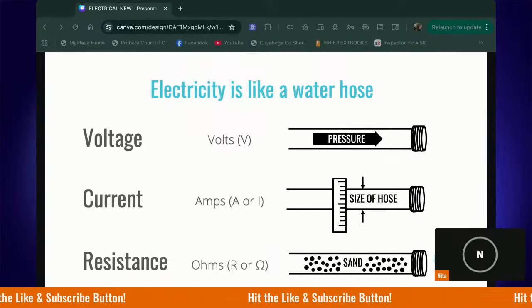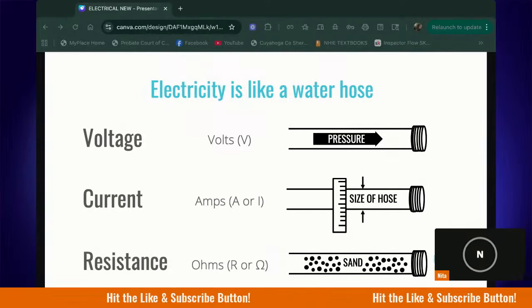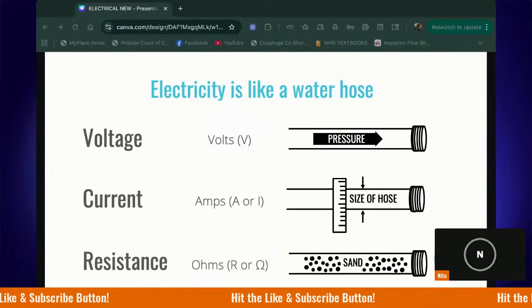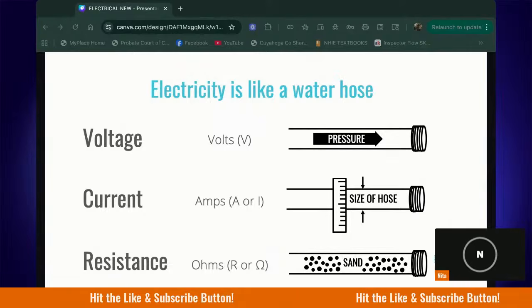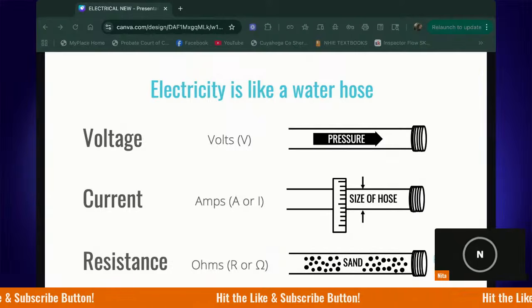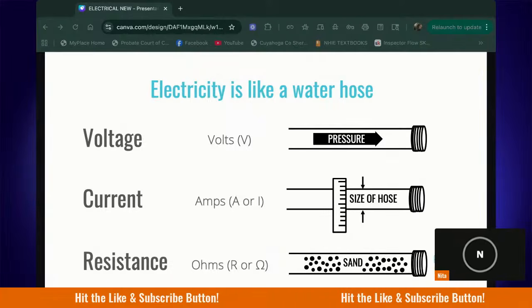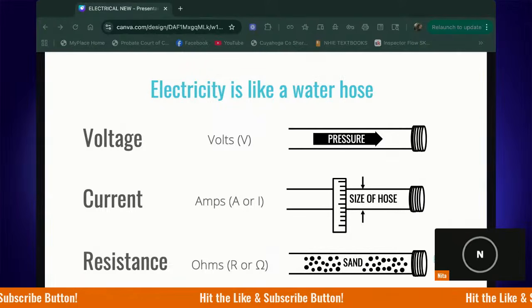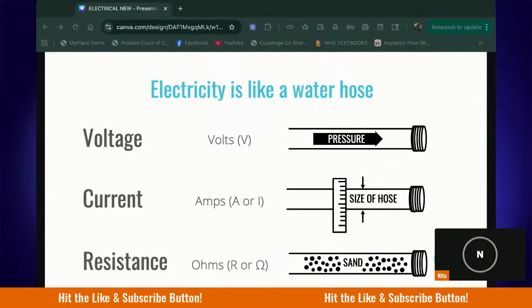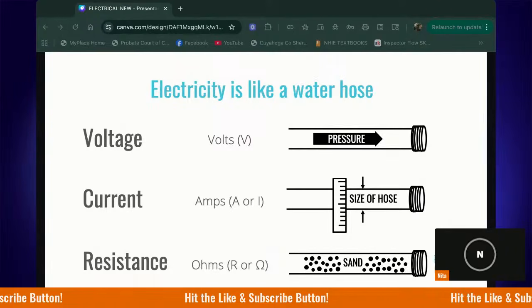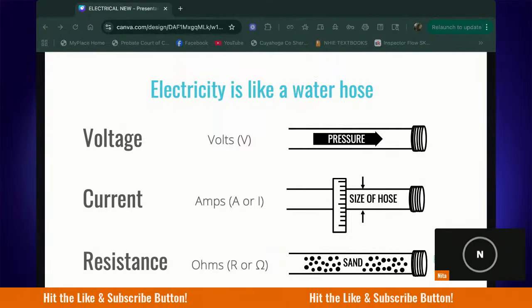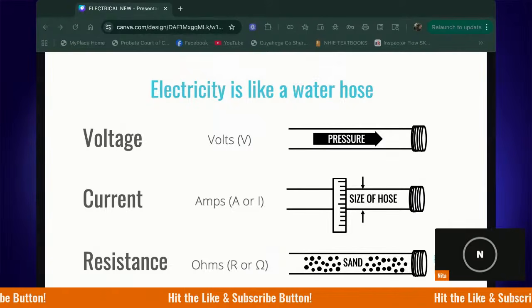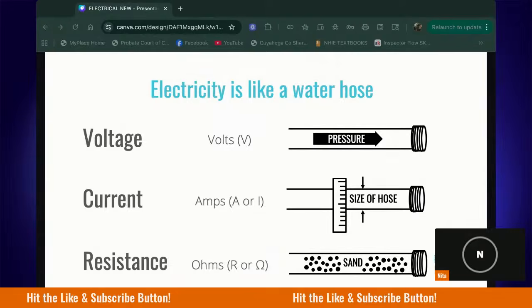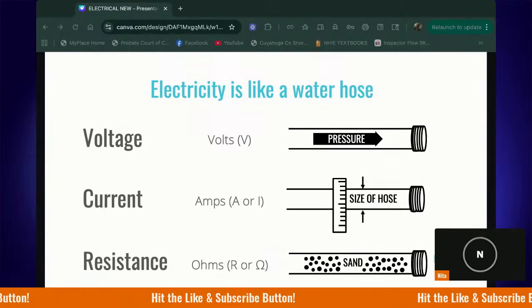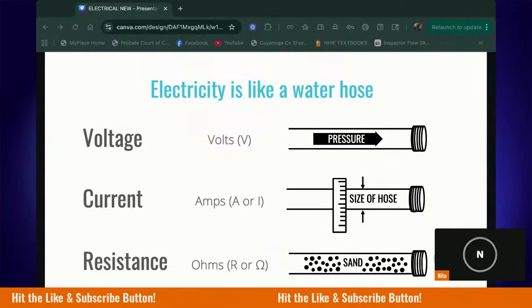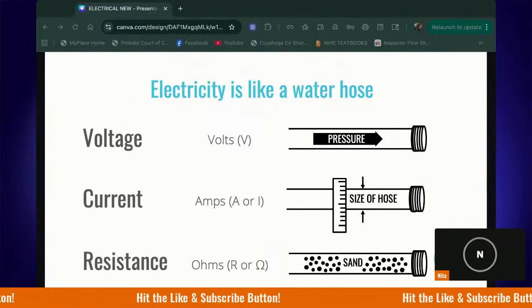So in our homes, most of our lights, our outlets, and smaller appliances are built to handle 120 volts. Okay, the larger items, your dryer, again, your AC, water heaters, ovens, all of that are designed for a 240 volt system. So remember when I said our low voltage systems, those use 12 to 24, like your doorbells, those little lights that you can put out in the yard, all of those are low voltage systems. So 12 to 24 volts compared to the 120 that it takes to actually light and use our outlets.